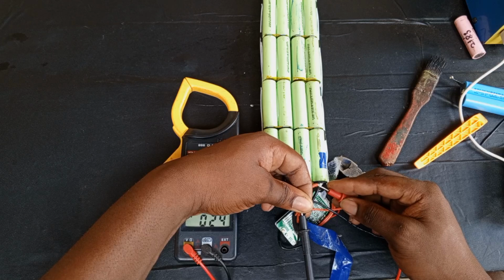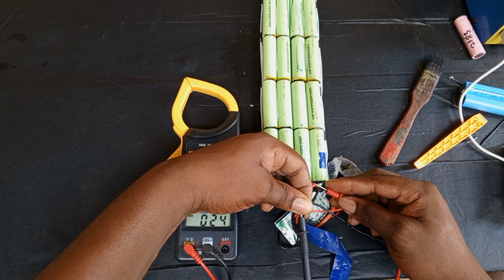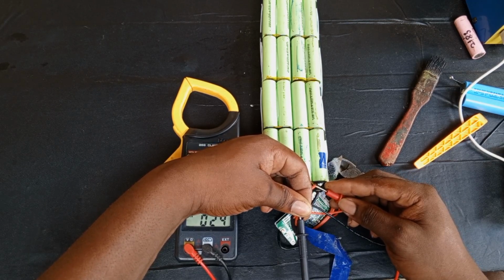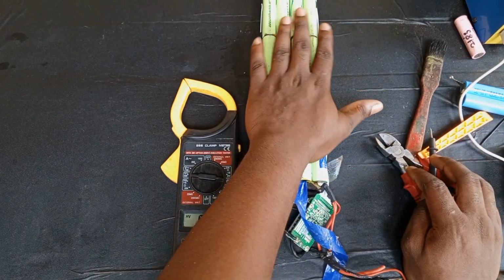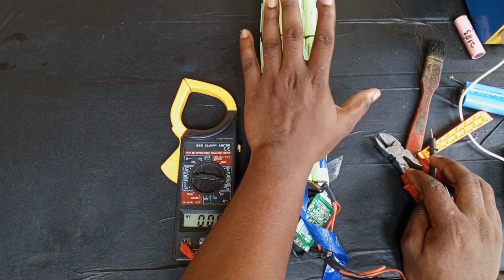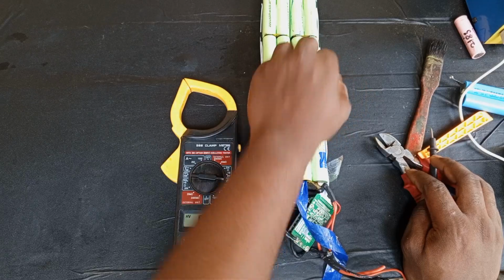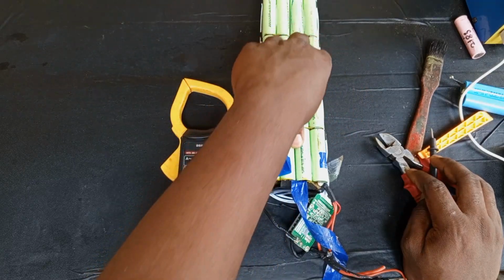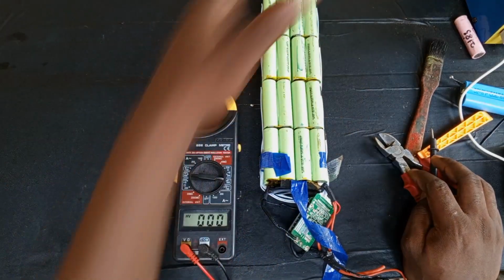From testing the probes, you can see the voltage I'm getting is 24 volts, which is bad because when this battery is low, the lowest voltage should be 29 volts. Since it's displaying 24 volts, that means there's an issue with some of the cells.